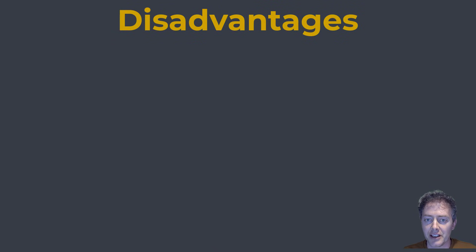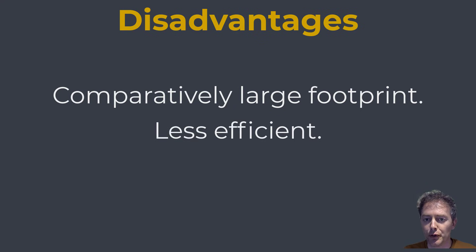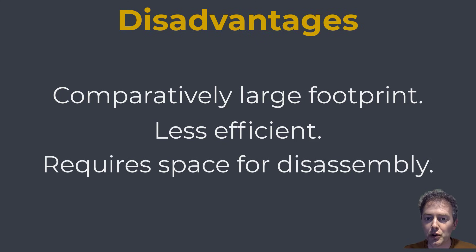There are, however, some disadvantages associated with shell and tube heat exchangers. The biggest is the large footprint they require compared to other types such as a plate heat exchanger. They're also less efficient for low flow and low temperature applications. Another inconvenience is that when you disassemble the heat exchanger to perform maintenance, you may require a lot of space — in order to pull the tubes out, the surrounding area needs a minimum of one tube length of space.